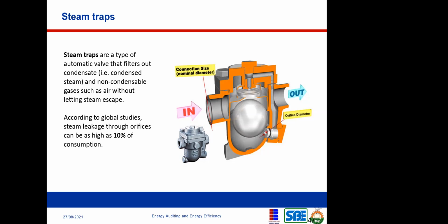That is one. Two, sometimes it can also fail to open. So steam condensate will build up and it will fail to open to allow the condensate to escape. In which case the condensate will remain inside your system, inside the steam, and it will affect the quality of your steam. You will not get the desired production output that you need, right? So the steam traps need to be taken care of so that they don't introduce their own inefficiency into the system.